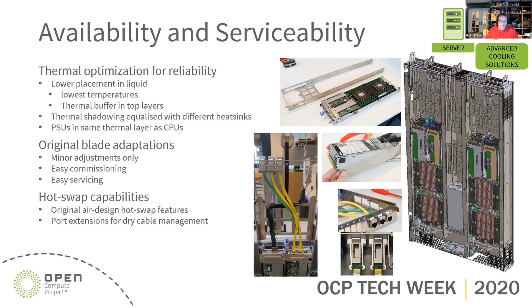This system is now hot swappable, fully serviceable from the liquid surface, and all the ports are extended for dry cable management. We're using port extenders both for the high performance network and the Ethernet interfaces, but also for the power cables. If you look at the power supply, how it's positioned, the power interface is redirected all the way above the liquid surface, so that everything is dry serviceable.